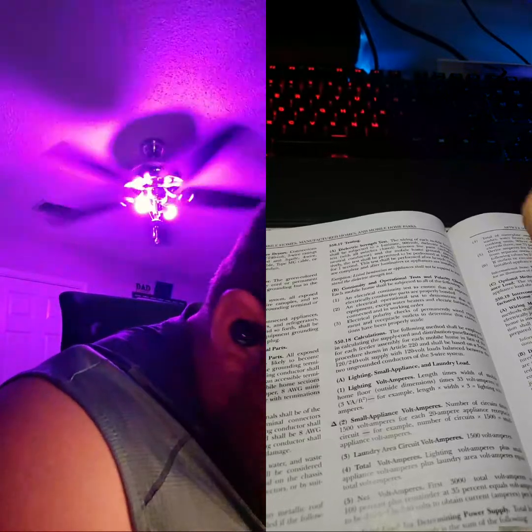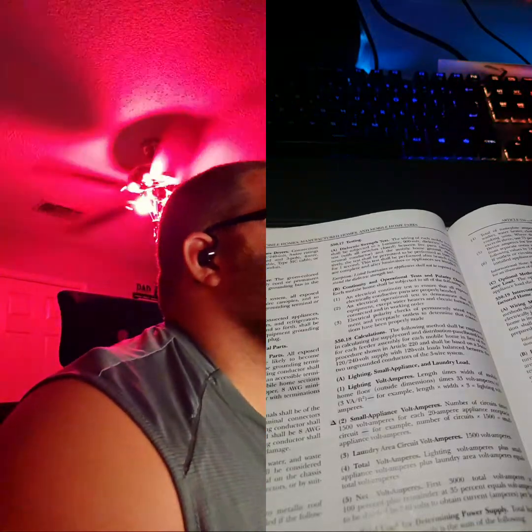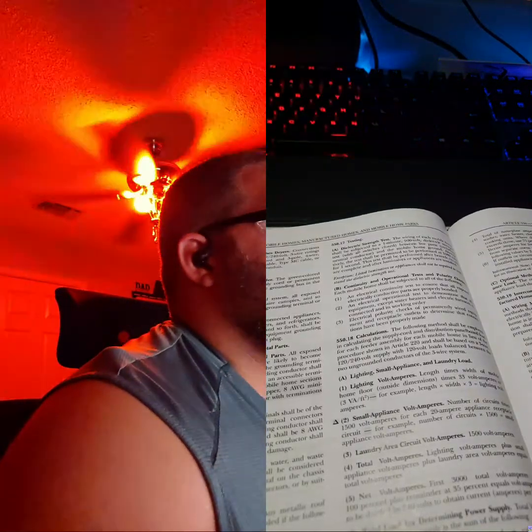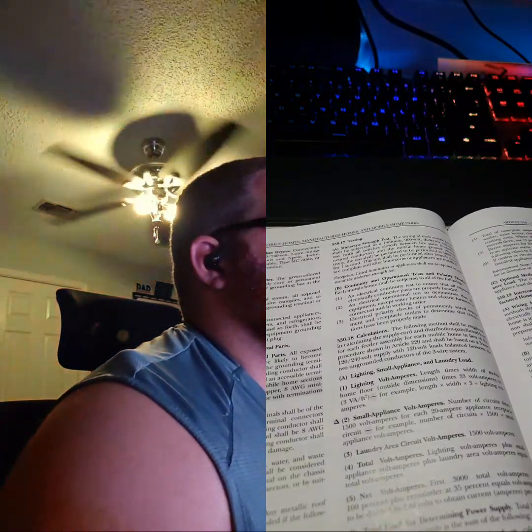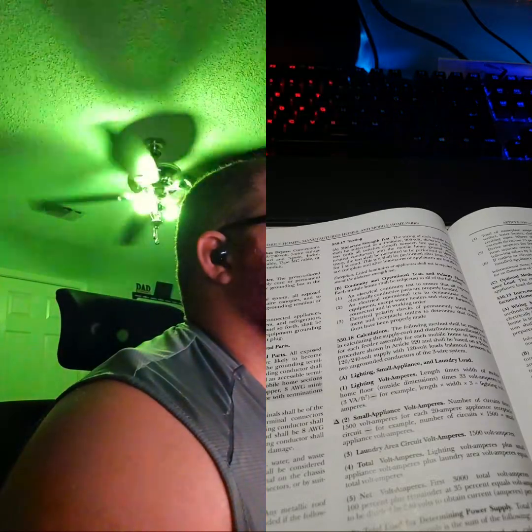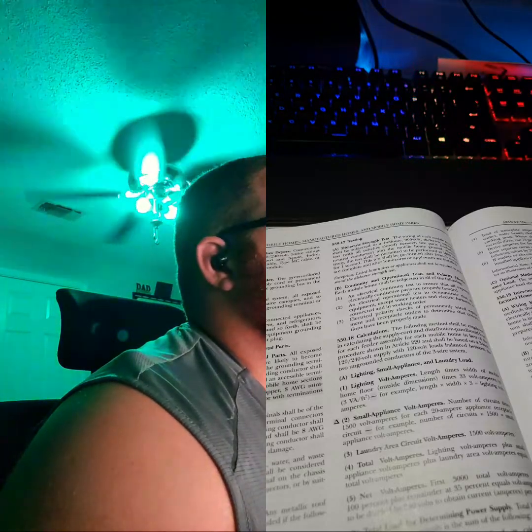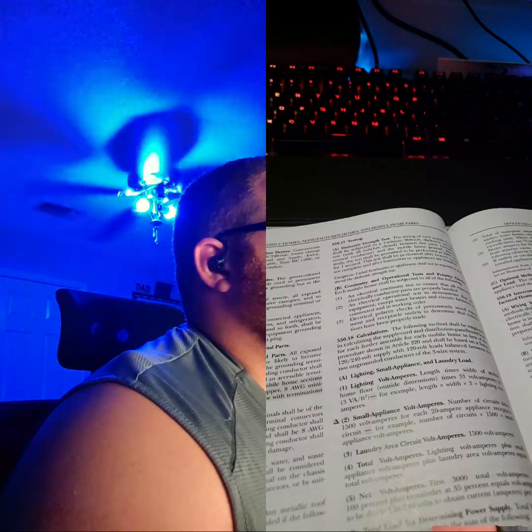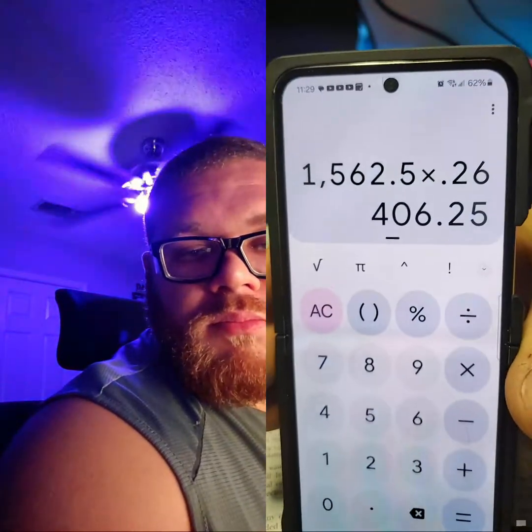What was it? You said 83? I still haven't done the math on that yet. 62.5 is 15,000 divided by 240, which is 62 and a half. Times 25 equals 1,562.5. And then times 0.26 equals 406.25, right? You multiplied it times 25? 0.25. Why did I do that? 0.26 because I'm an idiot.